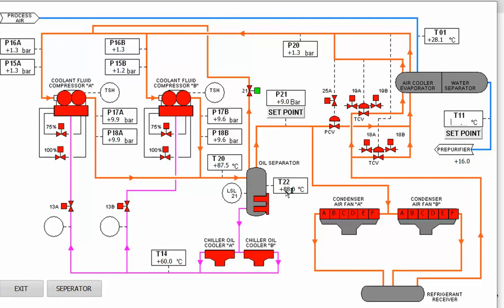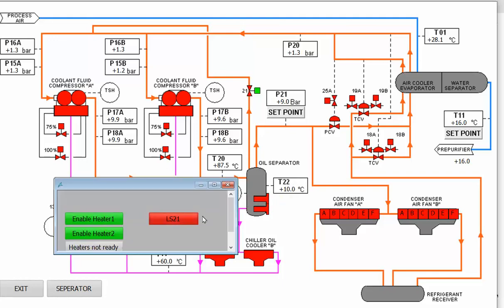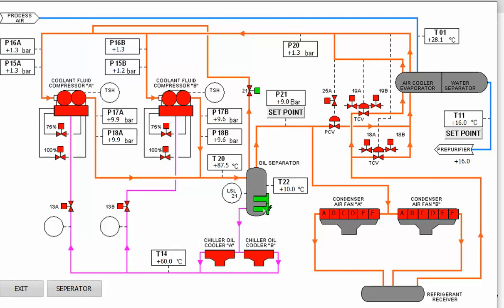Here I can function-test the heater if the temperature is decreasing, like to 20. In order to activate the heaters, we need to ensure that the amount of oil is sufficient in the oil separator. If the oil is not enough, heater 1 and heater 2 will not operate.